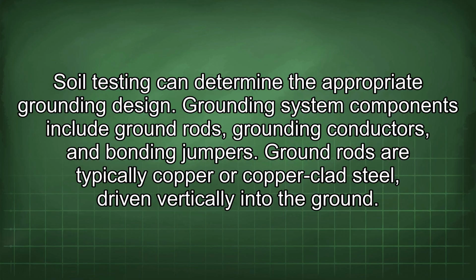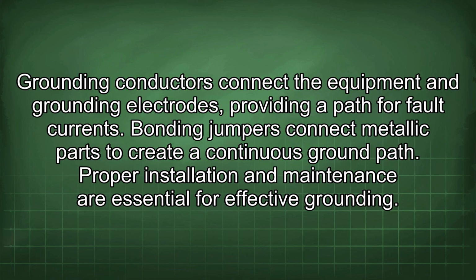Grounding system components include ground rods, grounding conductors, and bonding jumpers. Ground rods are typically copper or copper-clad steel, driven vertically into the ground. Grounding conductors connect the equipment and grounding electrodes, providing a path for fault currents. Bonding jumpers connect metallic parts to create a continuous ground path.